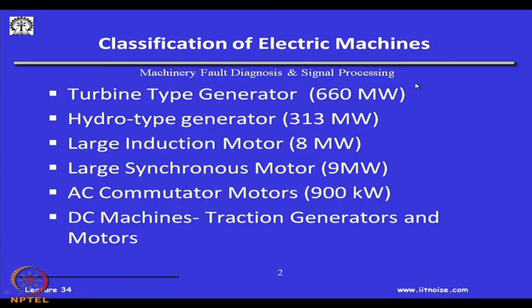So, if I was to classify the electrical machines, there could be many different types. By machines, I essentially mean a motor or a generator. Particularly if you go to the steam power plants or the hydro power plants, you will see large generators. Typical capacity of large generators would be around 660 megawatts, hydel generators would be about 313 megawatts and so on. And of course, if you go to plants, large rolling mills, etcetera, we will be having large induction motors or synchronous motors of around 10 megawatts in power. And then we have the AC commutator motor around 900 kilowatts. And invariably in many plants, steel plants, paper mills, cement plants, you will see these kinds of motors used. And this is the single most prime mover in the plant.